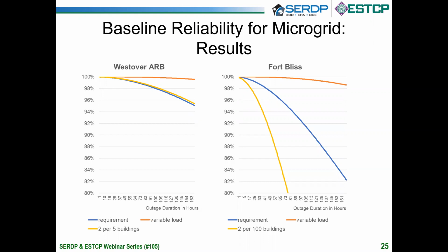the peak critical load. Now, one thing to point out about this is people often assume that they can get multiple nines of reliability for diesel-based systems, and that is a myth. It cannot be achieved with current technology. But the upper line in orange, labeled variable load, shows what an N+1 microgrid diesel-only system would provide in terms of reliability. As you can see, this is not multiple nines, but it is at least 2 nines throughout the duration.